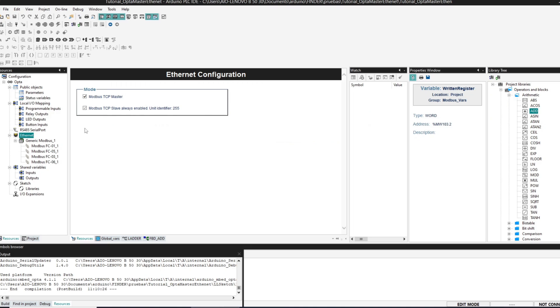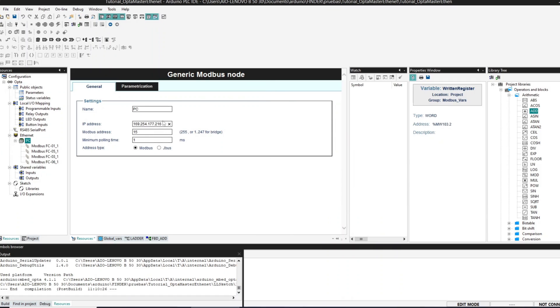In order to set up communications, we go to Modbus and here we write the PC, because that is the device we are going to be controlling as a slave. In the IP address field we must type the IP of the slave. To find out the address of our computer, we go to cmd and type ipconfig. Here we can see the address 169.254.177.216, so we type that in. Then we choose the Modbus address, which must be between 1 and 247 and identifies our slave — we write 20 for example.